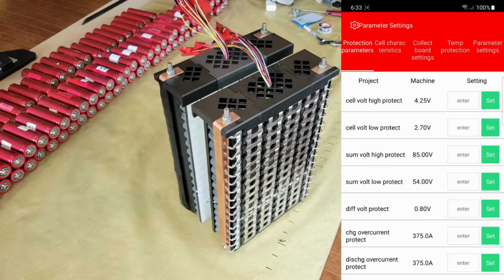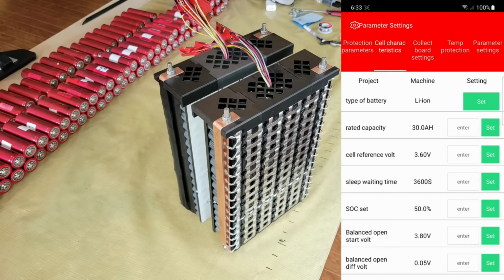The first section under the parameter settings shows all of the default protection settings like overvoltage and undervoltage, overdischarging and overcharging, cell volt difference, etc. Normally these are already programmed for the type of battery that you're working with, provided that you ordered the correct BMS for it, but it's always a good idea to verify that these settings are all correct before using the battery. The next section allows you to set the amp hour rating for your battery, the nominal voltage of your cells, and when you want to trigger balancing.